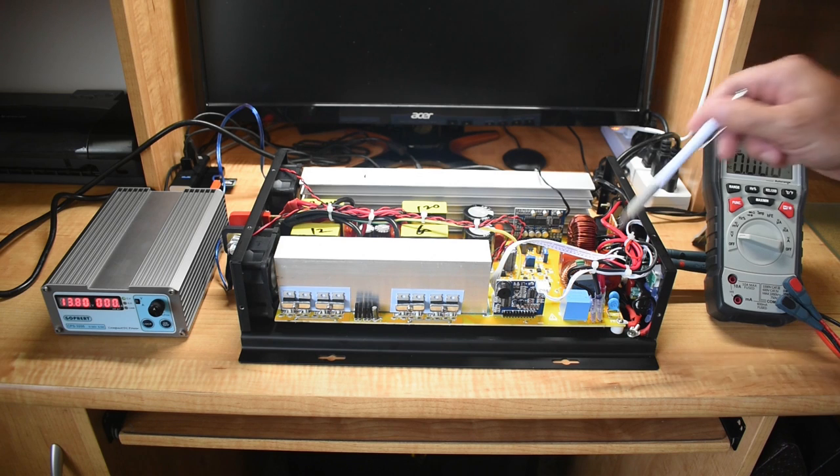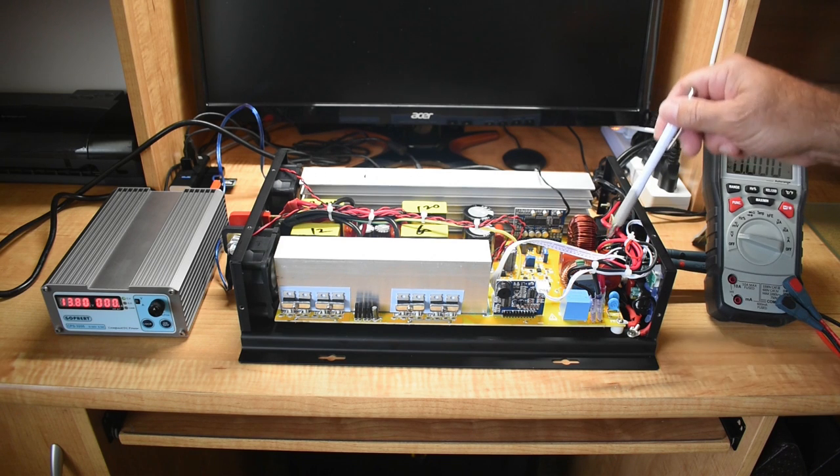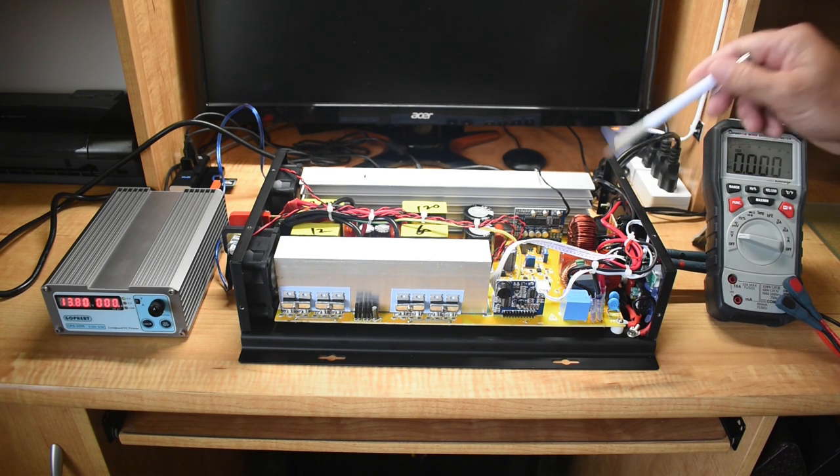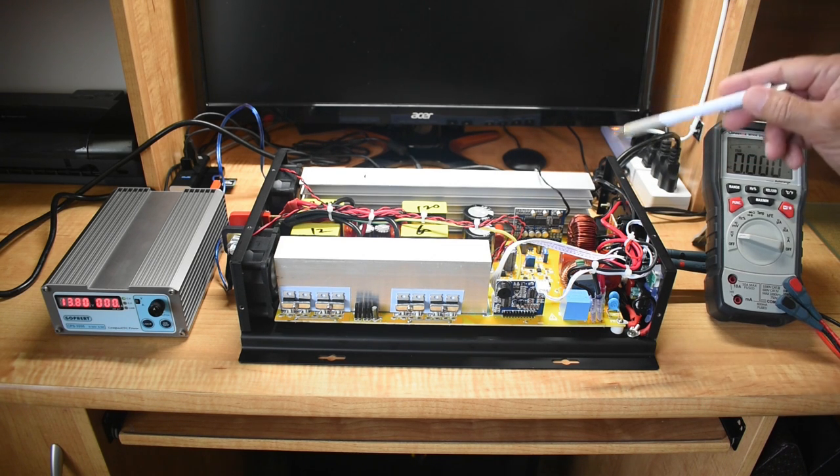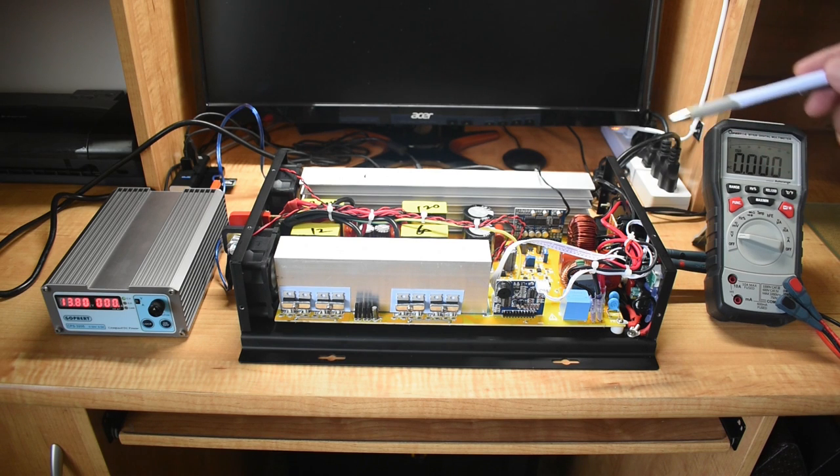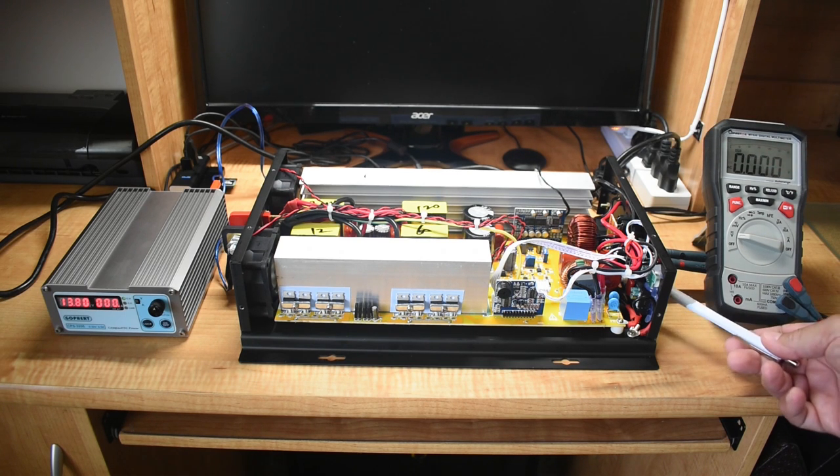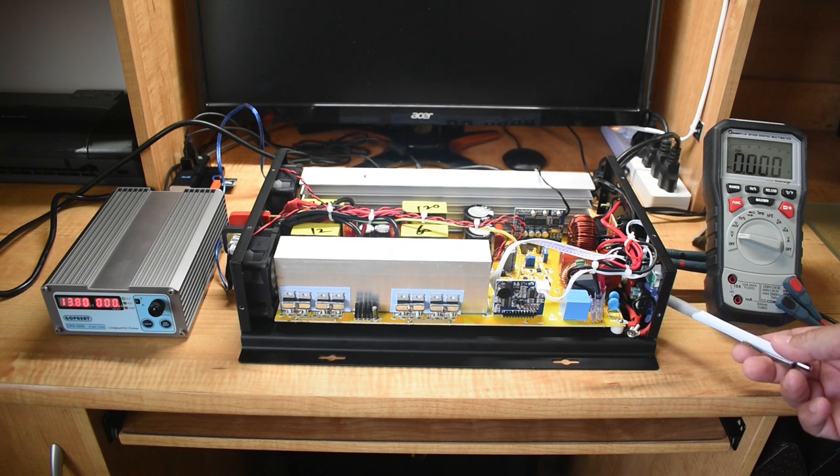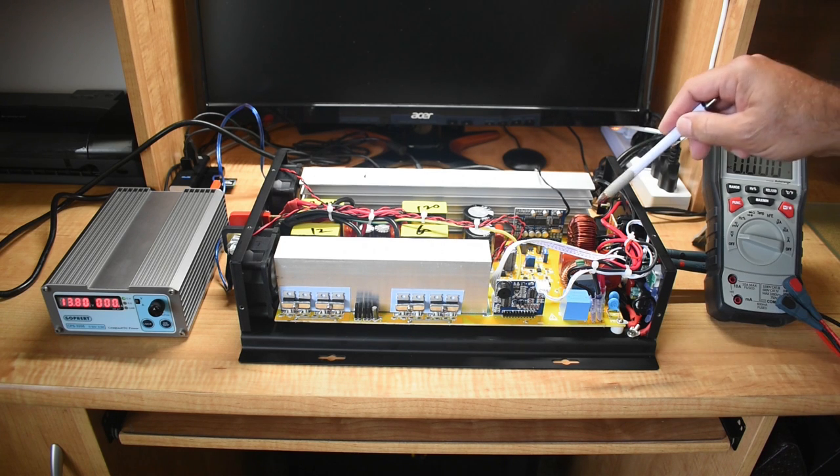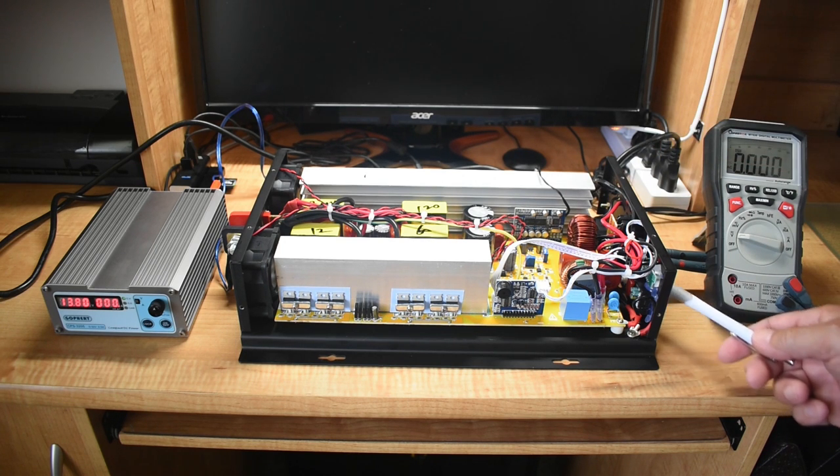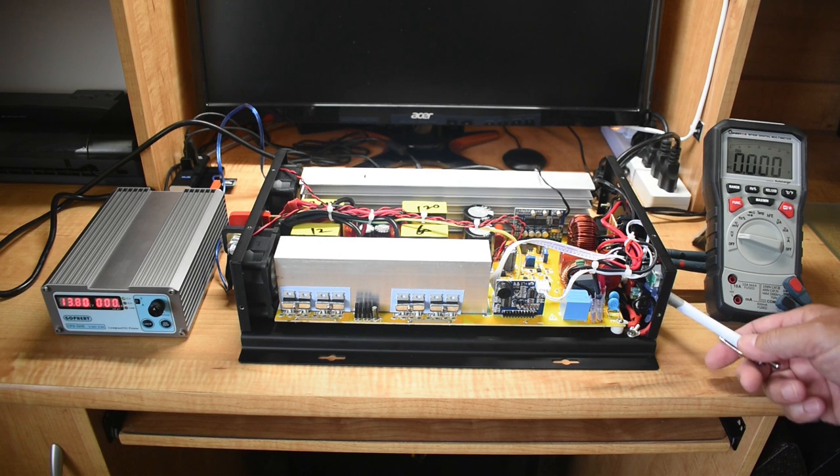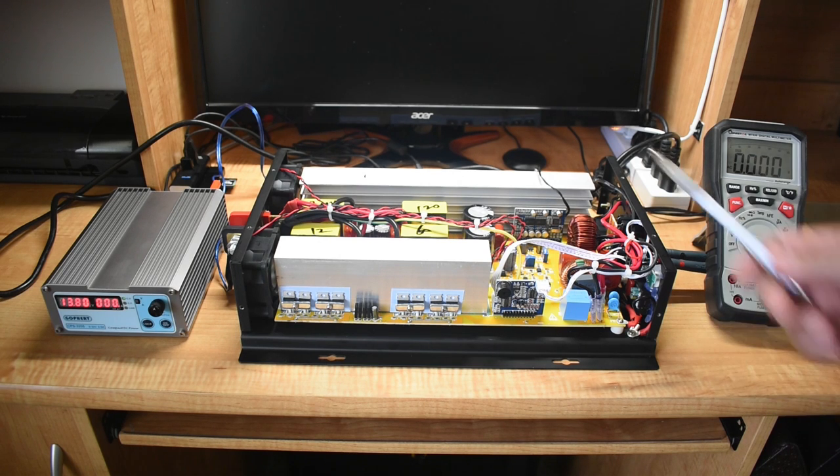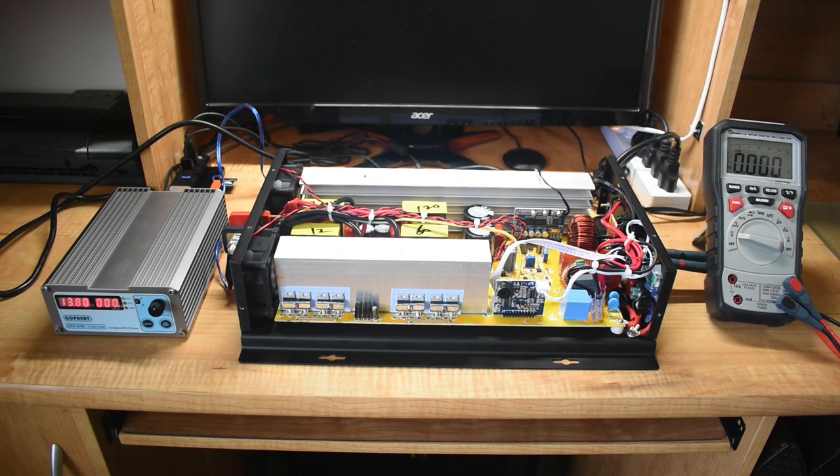As a result of the smaller wire going to the receptacle and the extremely high current drain coming off the 4D battery, it caused the voltage to drop to around 95 volts. If we use the heavier wire, it probably would have stayed around 100 or 105 volts, even with the heavy load.